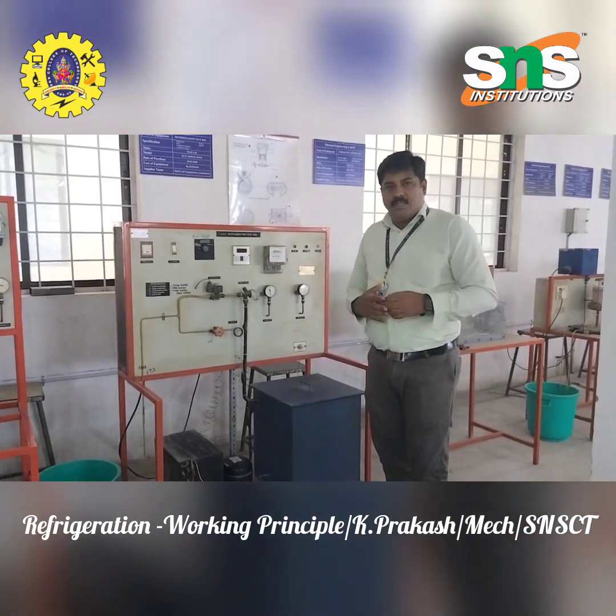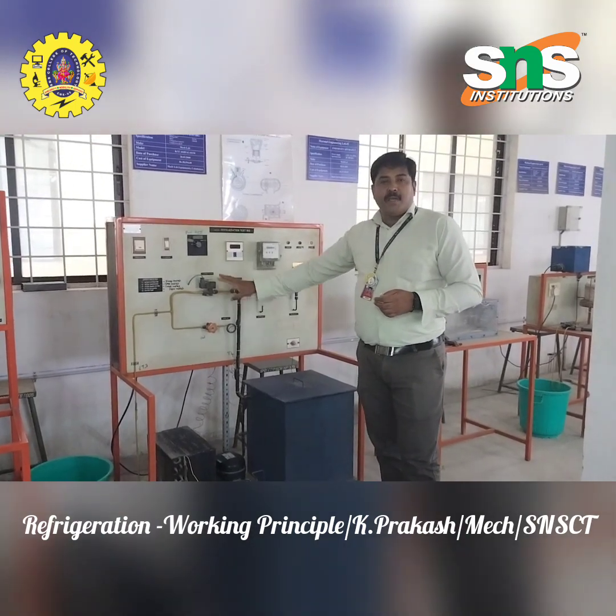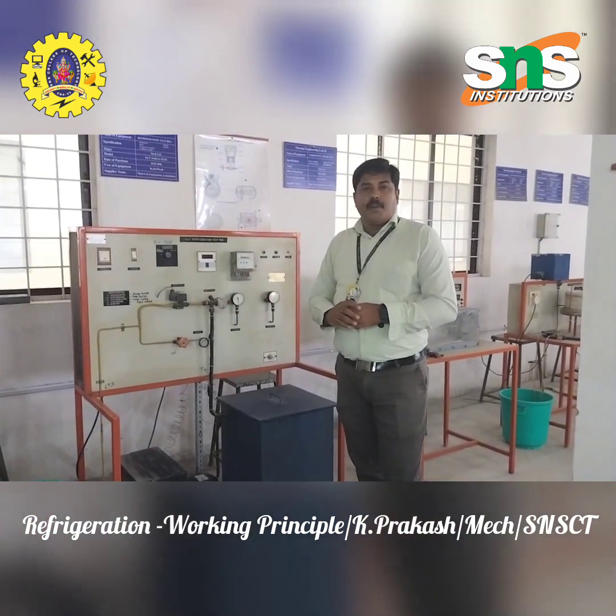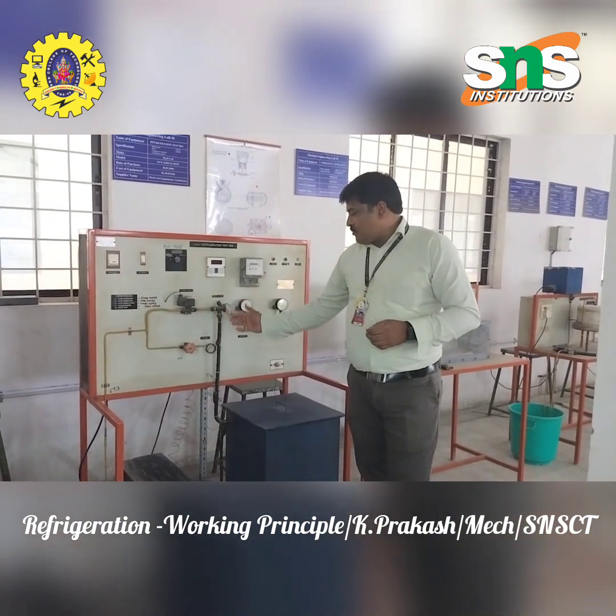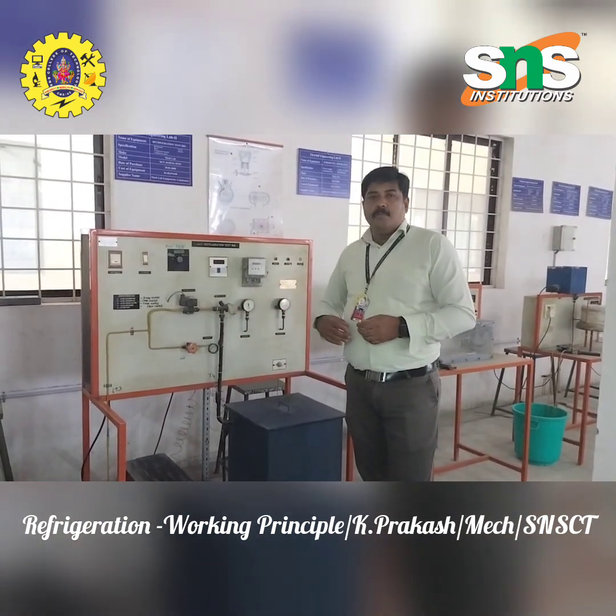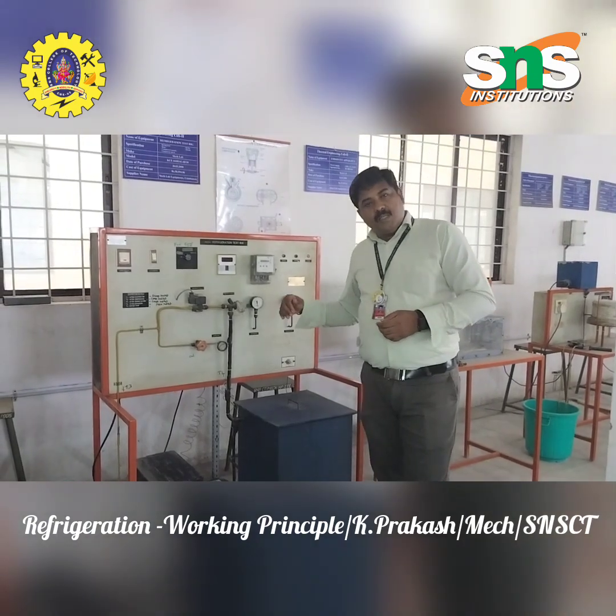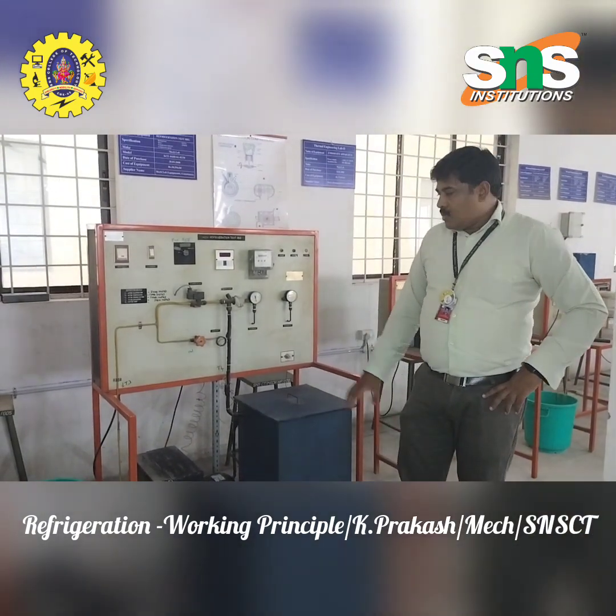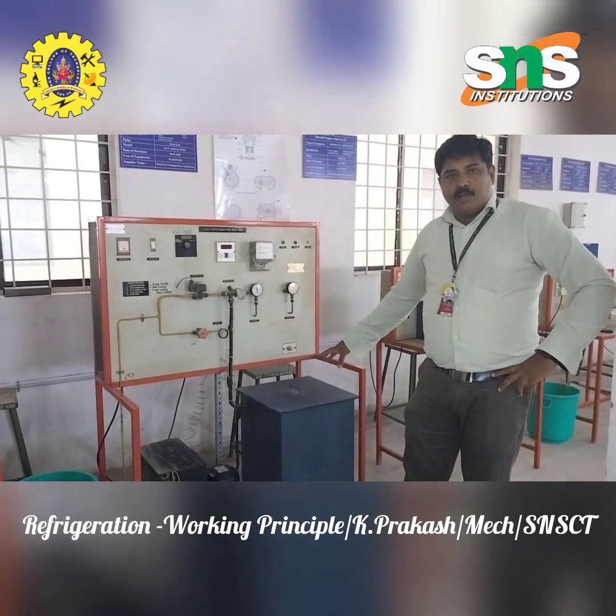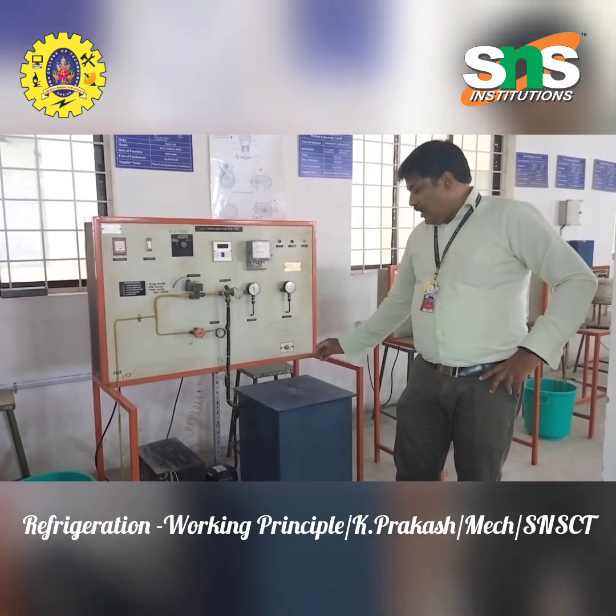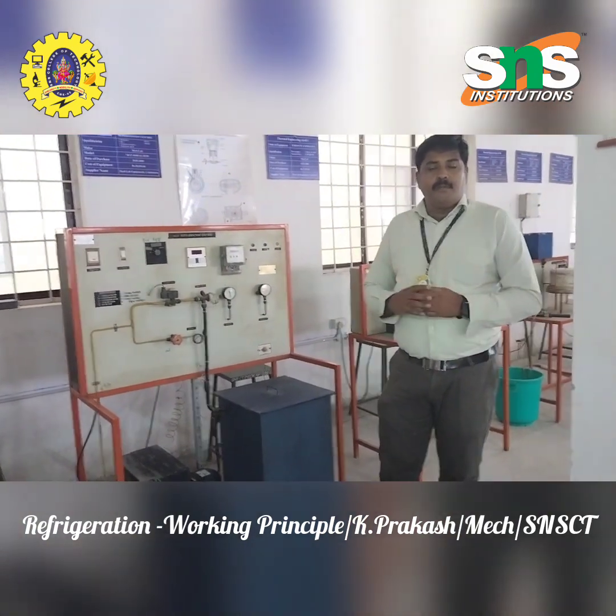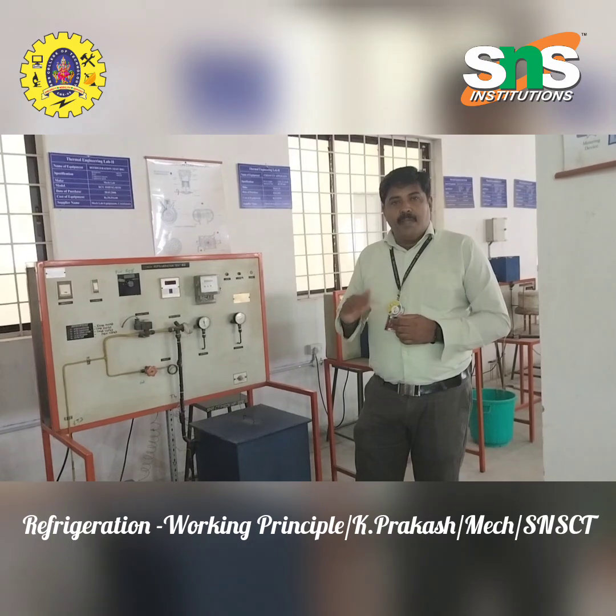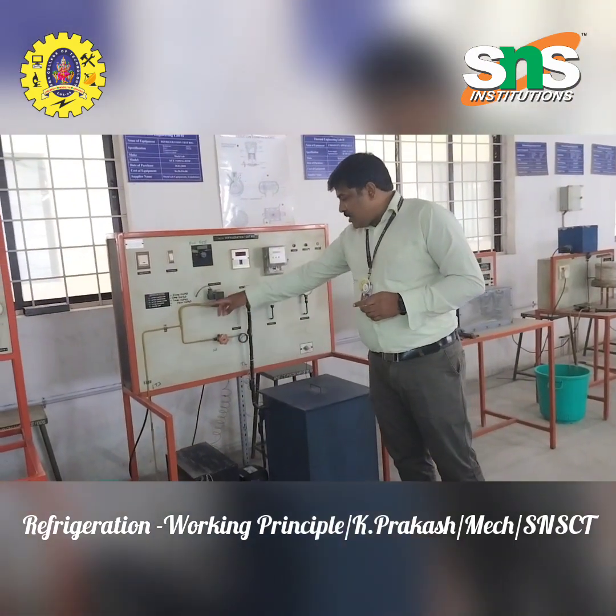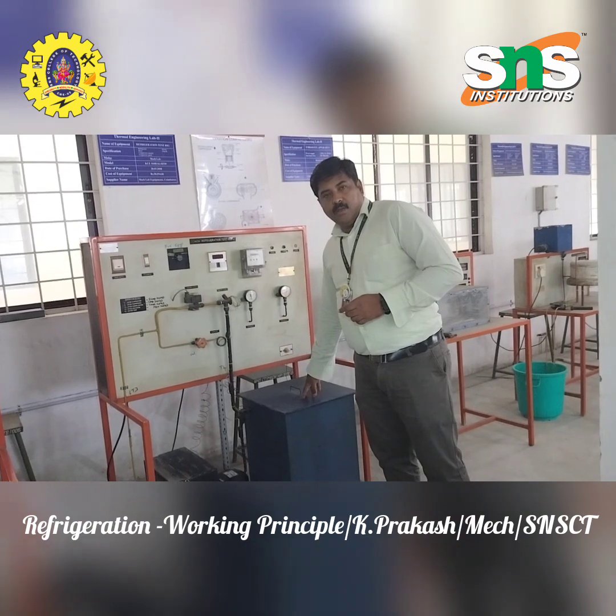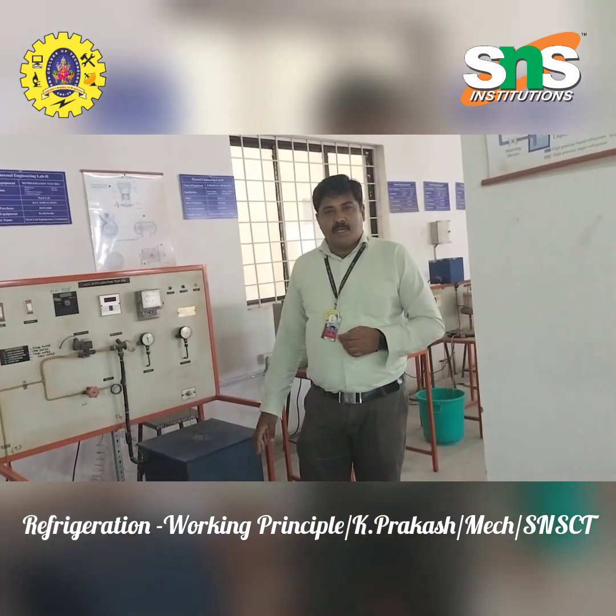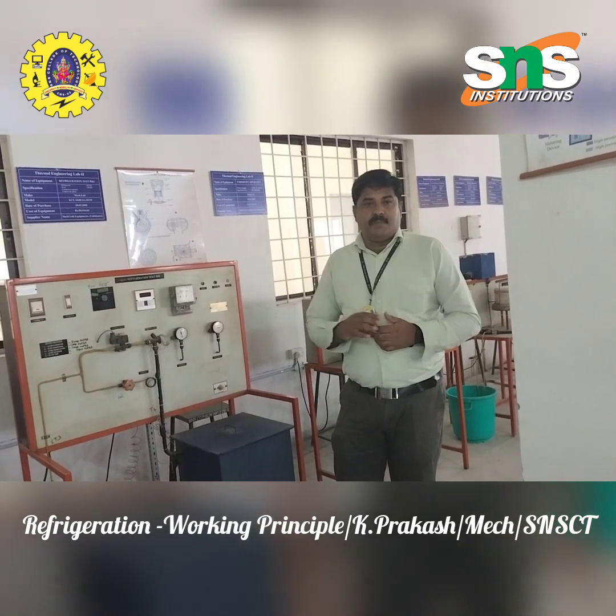Now we can ask what the need for the expansion valve in a refrigeration process is. Here we are using a capillary tube as the expansion device. What is the need for this capillary tube? When the refrigerant is compressed in the compressor, the pressure of the vapor refrigerant will be high. If it enters the evaporator at high pressure, the cooling effect will be lesser.